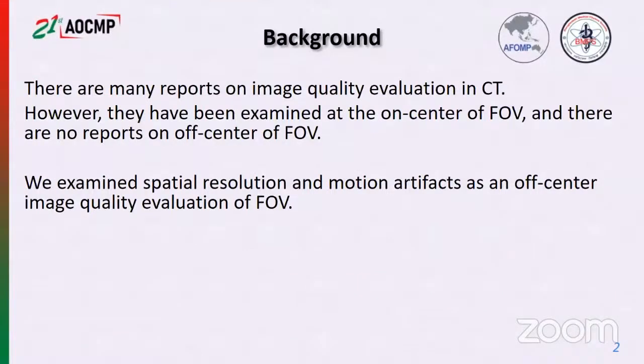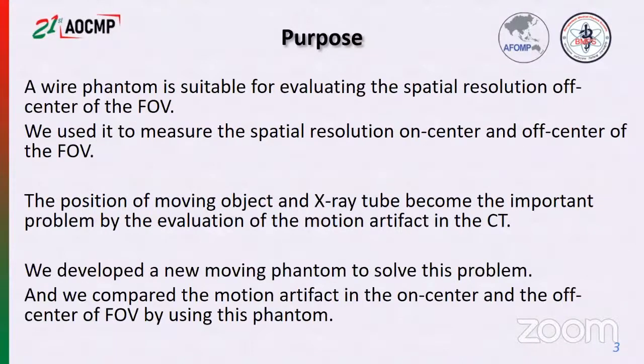Background. There are many reports on image quality evaluation in CT. However, they have been examined at the on-center of FOV, and there are no reports on off-center of FOV. We examined spatial resolution and motion artifacts as an off-center image quality evaluation of FOV. We propose that a wire phantom is suitable for evaluating the spatial resolution off-center of FOV. We use it to measure the spatial resolution on-center and off-center of FOV.